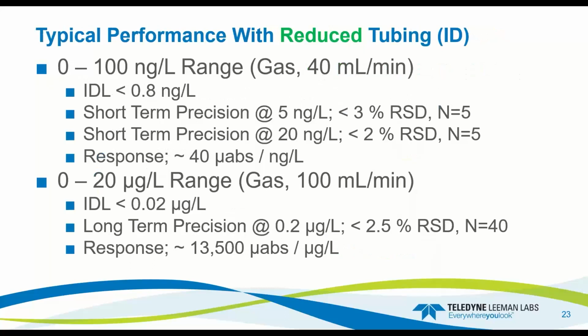So the typical performance of this new tubing harness is basically about the same as what we had with the original tubing. Your IDL is less than 0.8, typically around 0.6 or 0.7 ppt. Your short-term precision is still really good at 3% for a 5 ppt, N equals 5, and less than 2% for a 20, N equals 5. Your response is about 40 micro-absorbance per ppt.